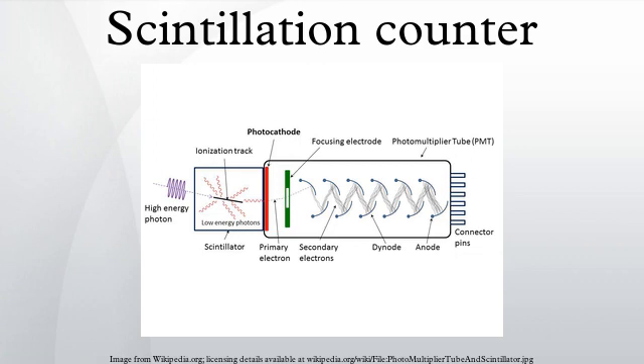For this, the scintillation counter with a large area scintillator window and integrated photomultiplier tube is ideally suited and finds wide application in the field of radioactive contamination monitoring of personnel and the environment.